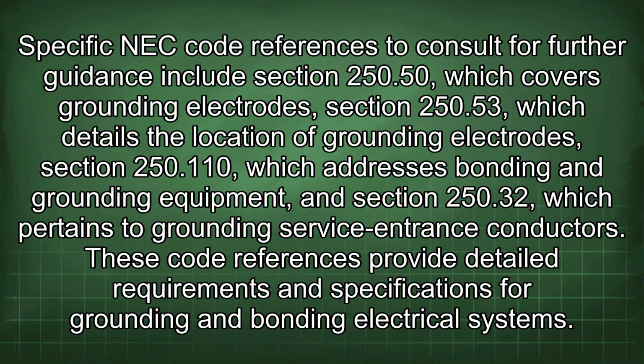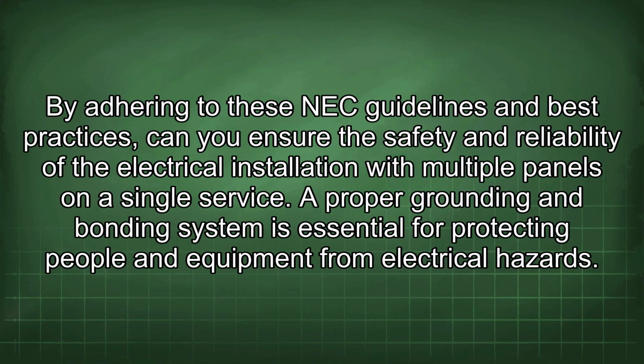Specific NEC code references to consult for further guidance include section 250.50, which covers grounding electrodes, section 250.53, which details the location of grounding electrodes, section 250.110, which addresses bonding and grounding equipment, and section 250.32, which pertains to grounding service entrance conductors. These code references provide detailed requirements and specifications for grounding and bonding electrical systems. By adhering to these NEC guidelines and best practices, you can ensure the safety and reliability of the electrical installation with multiple panels on a single service.